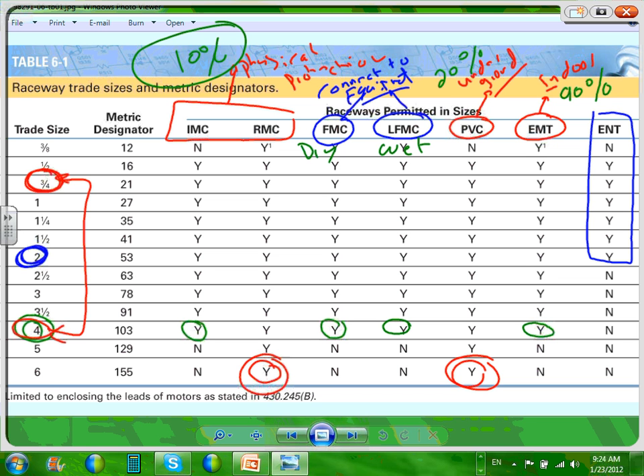It's non-metallic ENT, electrical non-metallic tubing, and the boxes are non-metallic. So the only metallic things you have are the hots and the neutral bringing the power, and the equipment grounding conductor, which is insulated and tied all the way to the surface. So that's a good application where interference is a big deal.